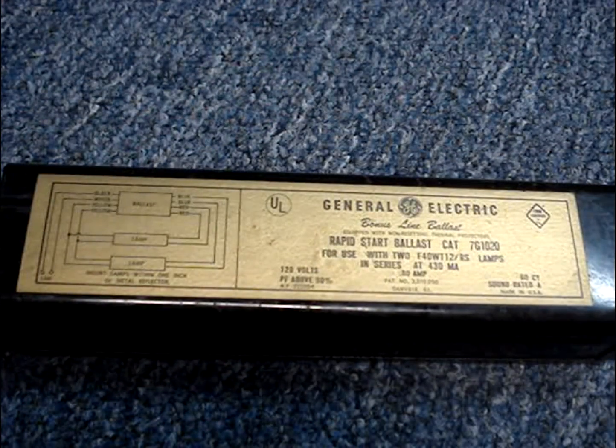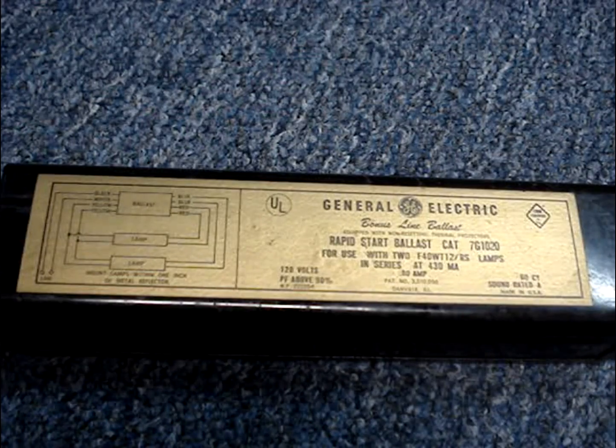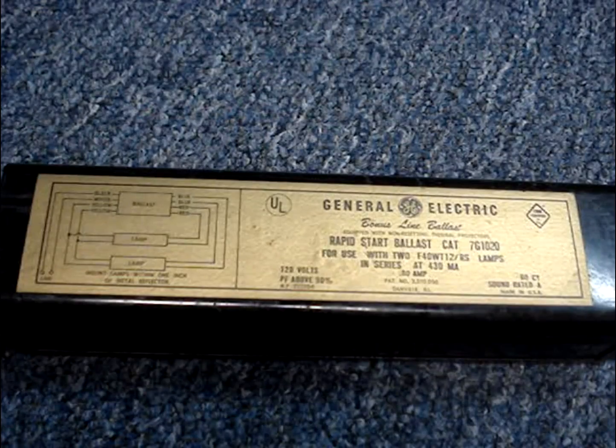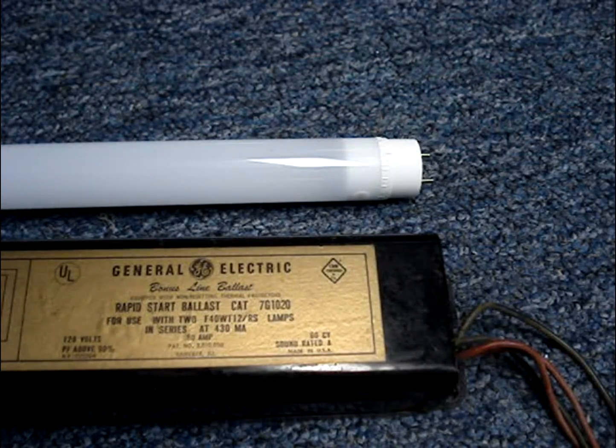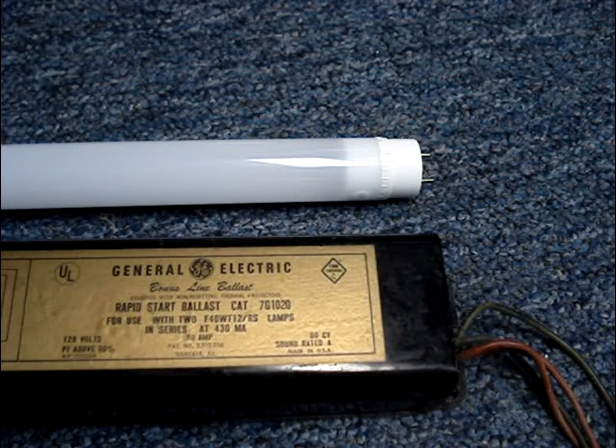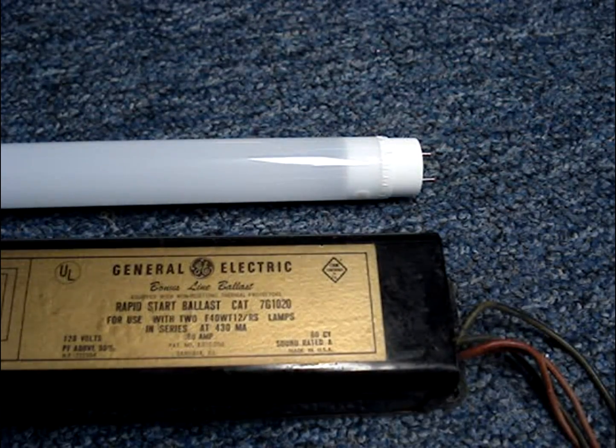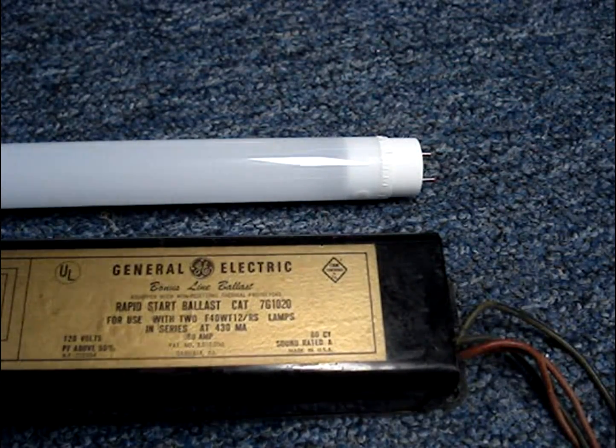The downsides are that if the ballast fails, you'll have to replace it. The tubes may not work with your ballasts and you may not get the energy savings claimed by the manufacturer. I tested a pair of plug-and-play tubes with my ballasts and I saved only 14 watts per two tube fixture. I have a video of my test. I'll put a link to that test in the box below this video.